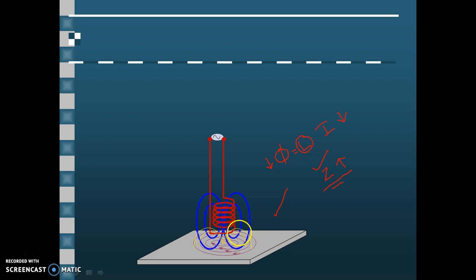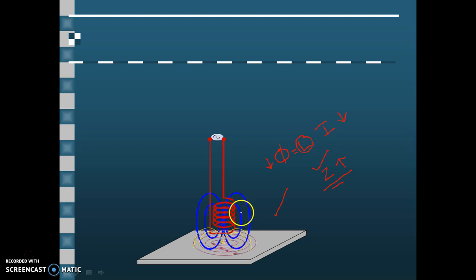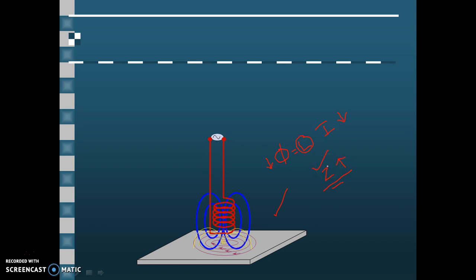Similarly, we can get an idea of the thickness of the sheet. If the thickness of the sheet is more, the eddy current produced will be more, so the electromagnetic field produced by the eddy current will be more, and the overall decrease in the electromagnetic field of the system will be more. Thus phi will decrease more and Z will increase more. For a thicker sheet, Z will increase more. For a thinner sheet, Z will increase by a lesser amount, because the produced eddy current will be less.